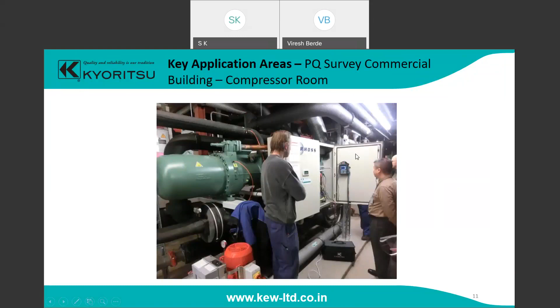And you can just measure with a single phase two wire system. We also have three phase three wire systems - you can just connect and measure. We have three phase four wire system also. We have also three phase four wire plus clamp for neutral, and three phase four wire for leakage clamp also.